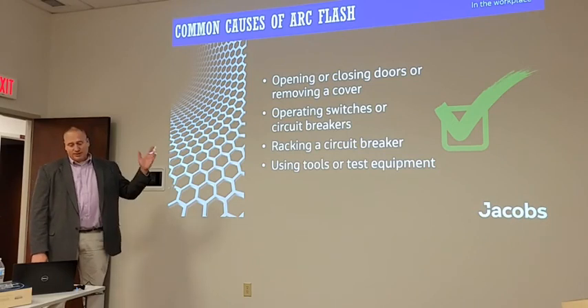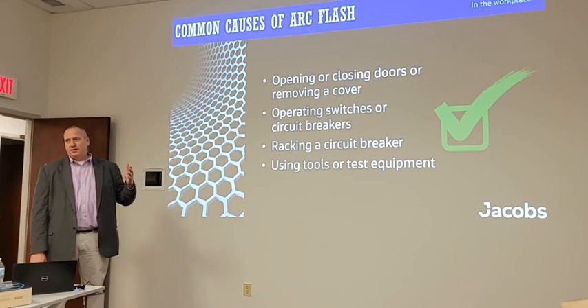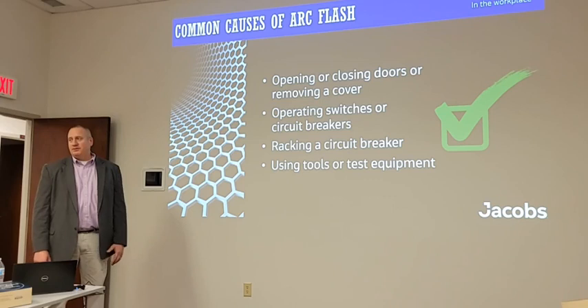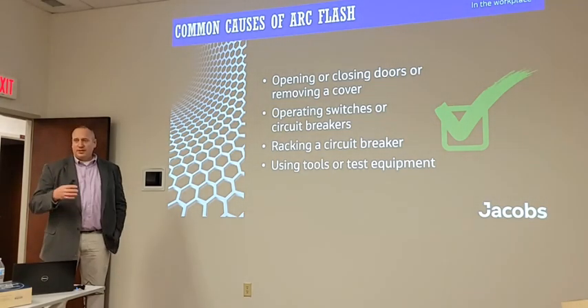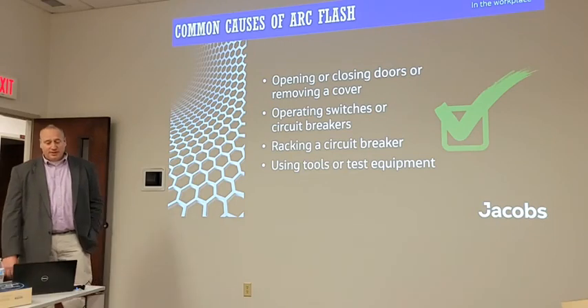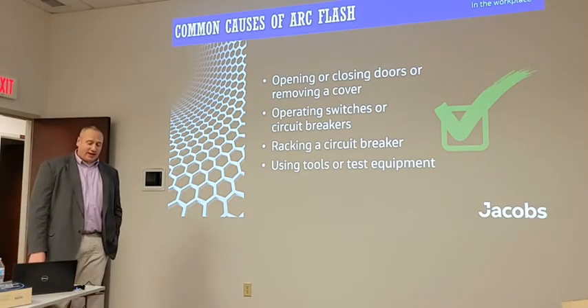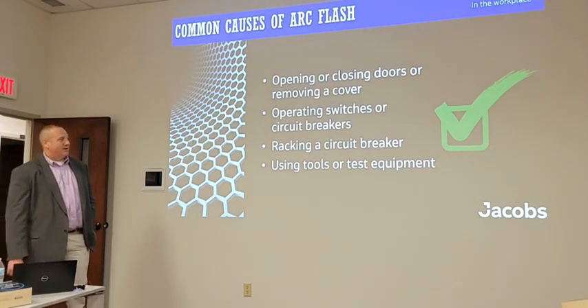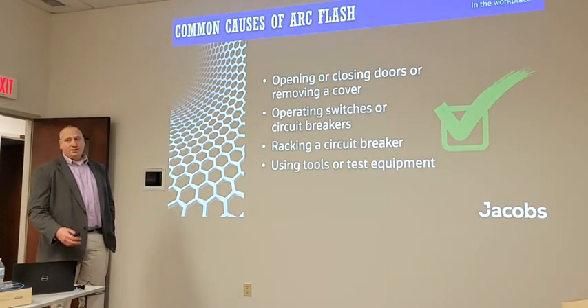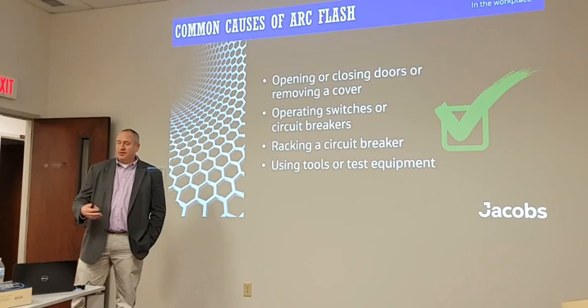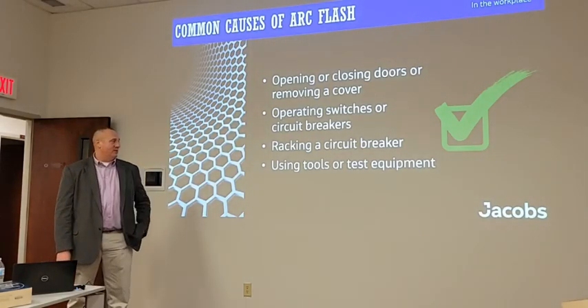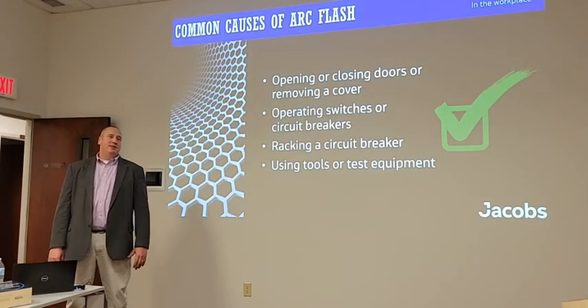Operating switches or circuit breakers, multiple things can happen there. You could be closing in on a fault, not realizing it, or anytime there's mechanical movement, there's an opportunity for failure of a part that could break and short phase to phase, breaking down that medium. So operating equipment can cause the arc flash. Racking a circuit breaker, to me, is one of the most risky things you can do on a distribution system, is racking a breaker on or off an energized bus. Then using tools or test equipment could inadvertently cause a fault.